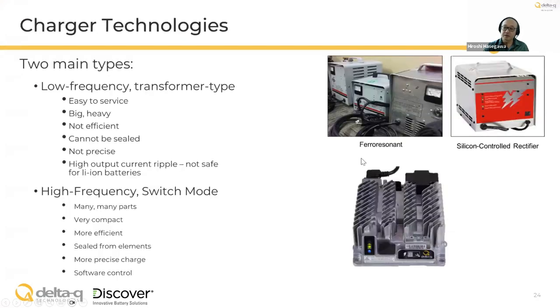There are two main types of chargers in the marketplace: low frequency, such as ferroresonant or SCR chargers, and high frequency, or switch mode chargers. Ferroresonant chargers have been around for a very long time and are still in service due to their simplicity. They use a transformer to control the charge with a timer or monitor circuit, and this simplicity also means they're big and heavy, not particularly efficient, and not particularly precise. However, they tend to be easy to service, though they may need frequent service if exposed to extreme conditions.